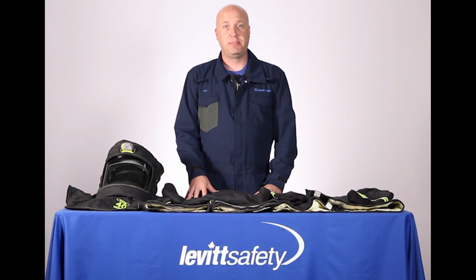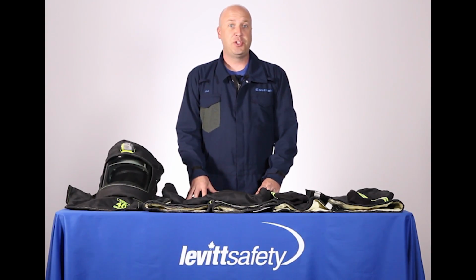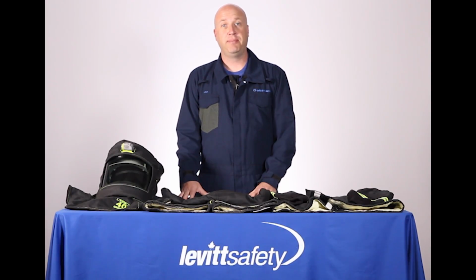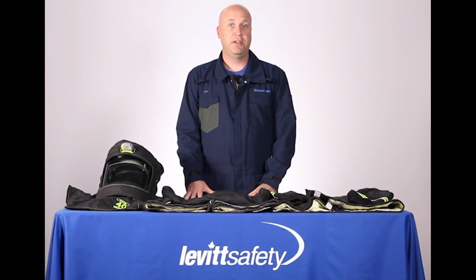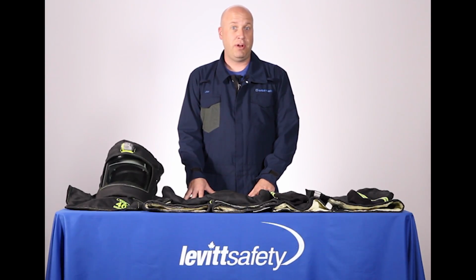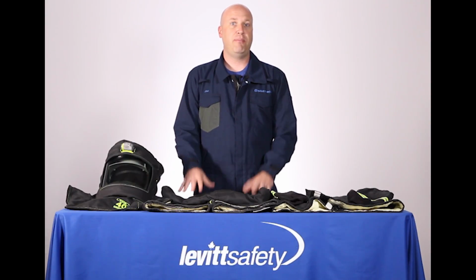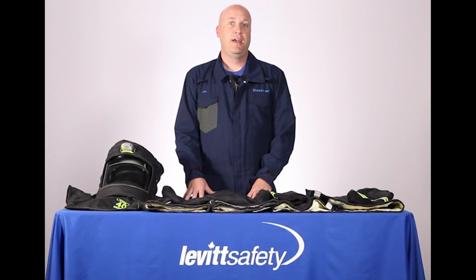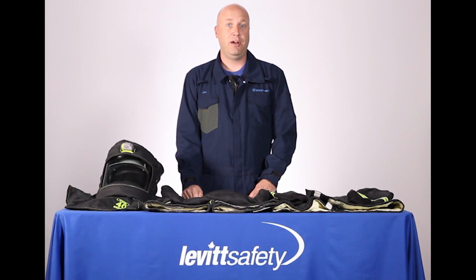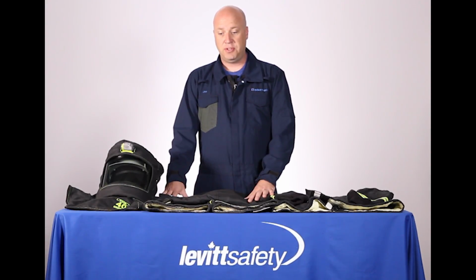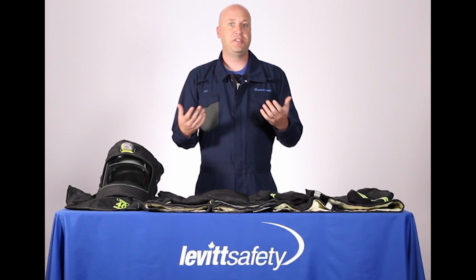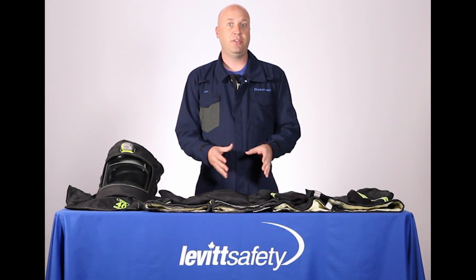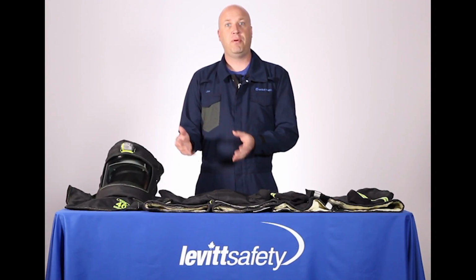Once you've completed your previous inspection, it's then time to make sure that you're ready to wear the arc flash suit. The standards require that you wear natural fiber clothing underneath your suit or your arc-rated clothing. I have on my arc-rated coveralls. I'm ready to go. What's really important to remember is not to ever wear meltable materials. So fabrics that are made of meltable or synthetic fibers, that's the rule of thumb when you're wearing an arc flash suit. When you're ready to wear the suit, make sure you have on your fall protection harness, your cooling vest, anything that is on underneath the suit is part of the preparation before you start to wear the arc flash suit.